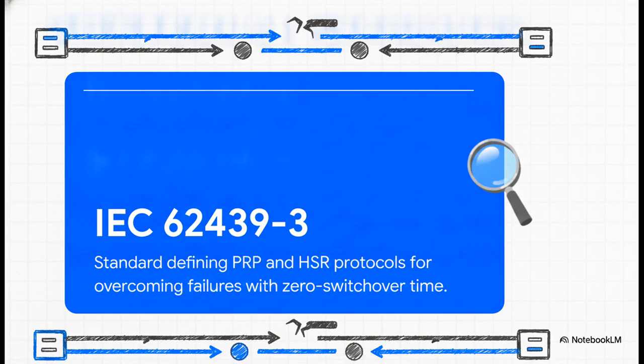This brings us to the IEC 62439 standard, which actually defines these two complementary protocols. Both of them completely bypass that traditional detect and reroute delay. Why? Because the redundant path is already carrying the exact same data in parallel. There's zero switchover time because there's nothing to switch over to. Let's look at exactly how each of these ingenious methods actually works.